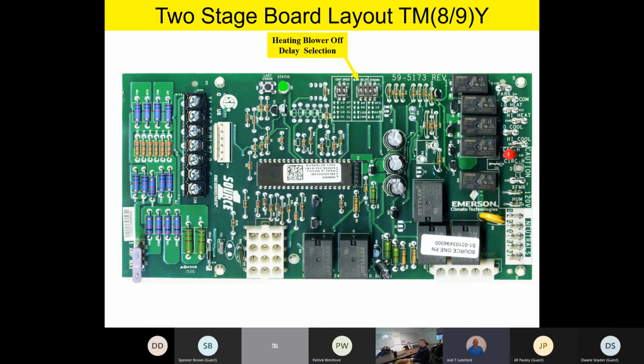Right next to that is our heating blower off delay selection. Now, normally, team, we ship these at about 120 seconds. This is the amount of time the indoor blower runs after the call for heat goes away. As you well know, once the call for heat goes away, the indoor fan continues to run a little while to distribute the heat off the heat exchanger into the conditioned space, because there's no reason to waste that heat, but it also cools the heat exchanger down. So this is field selectable, how long that fan runs after the call for heat goes away.